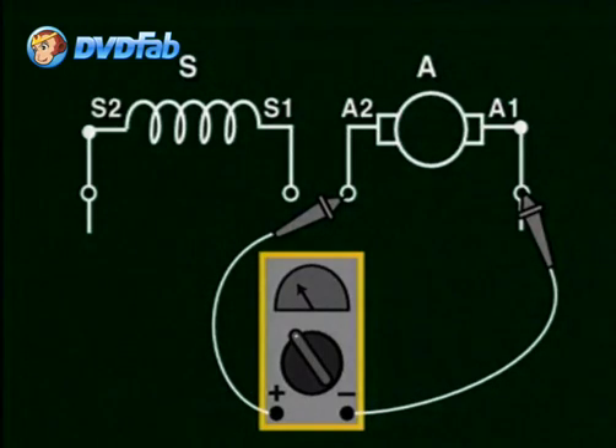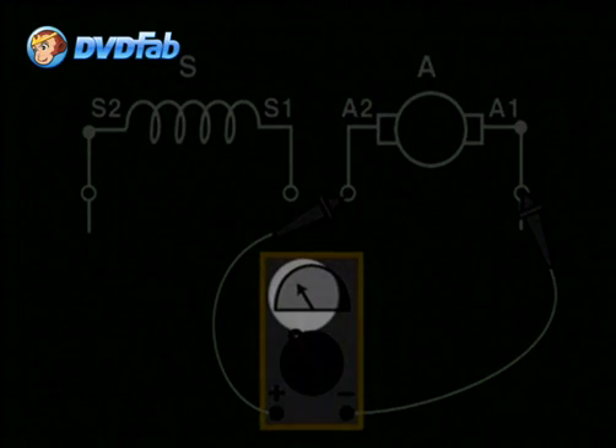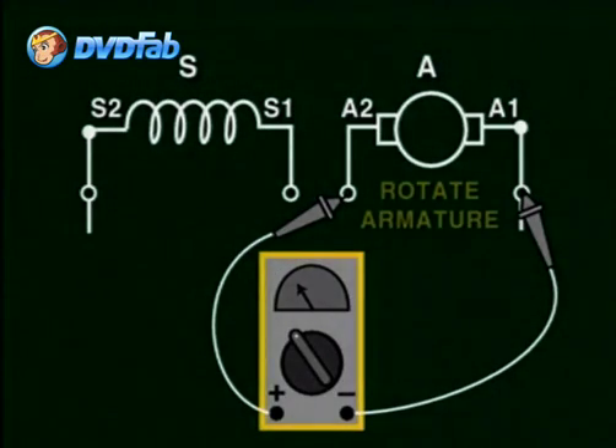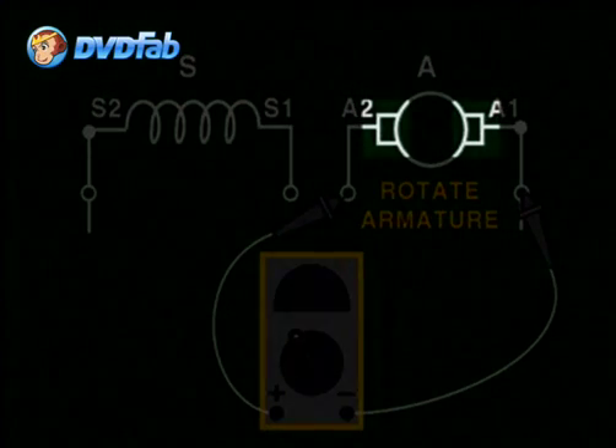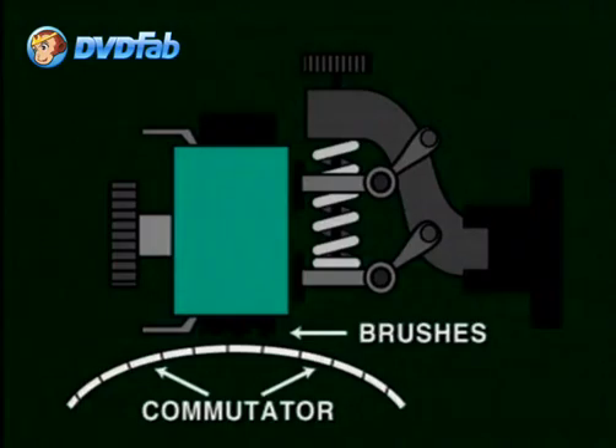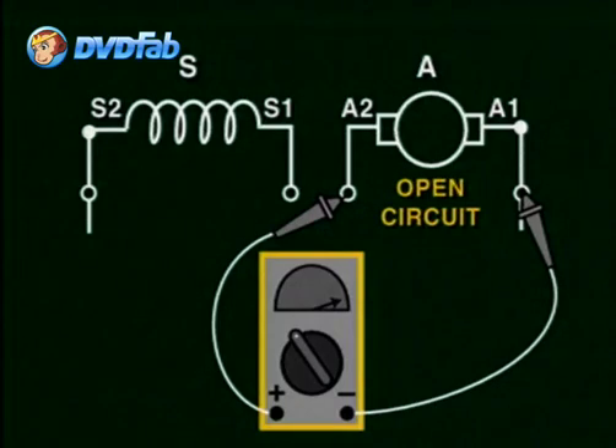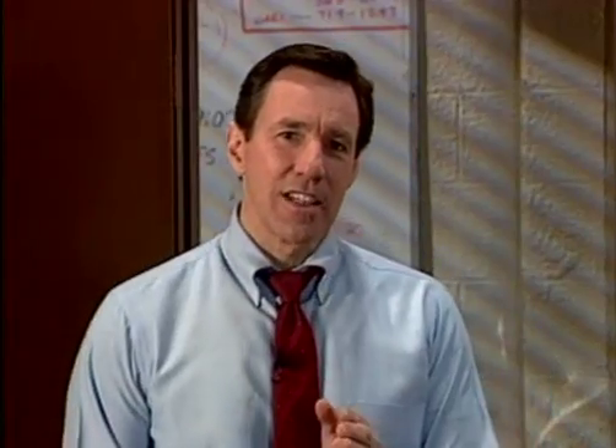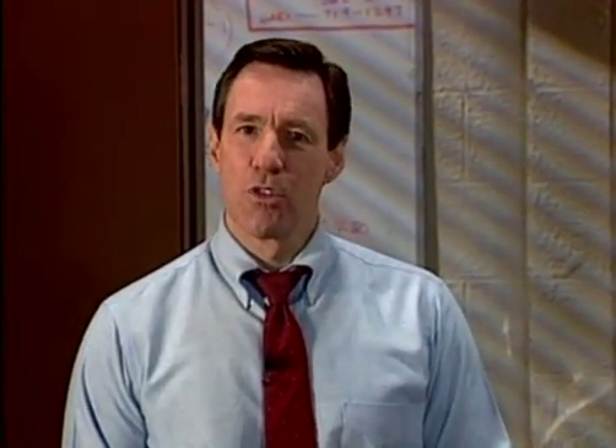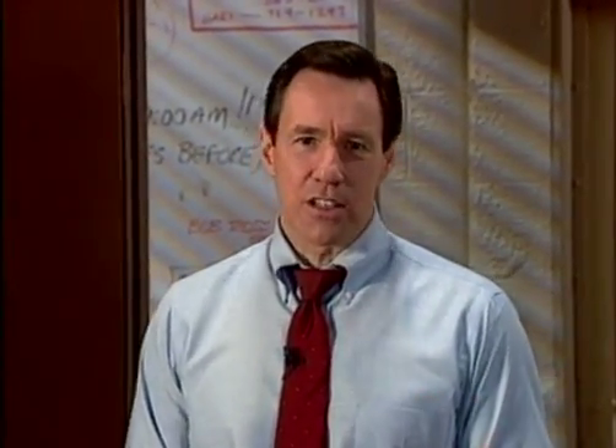To test the armature, we place the ohm meter between terminals A1 and A2. If the reading shows a resistance in ohms, there is continuity. You should now start rotating the armature shaft slightly so that you can detect possible bad spots where the commutator may have an open or the brushes may not be properly seated. If the ohm meter shows an infinity resistance reading, an open circuit is detected. Continue testing the brushes and the commutator visually for damage. After detecting an open in the armature coil, you should remove the armature from the frame for repair. The armature can be turned on a lathe by a machinist, and if needed, the brushes can be replaced.